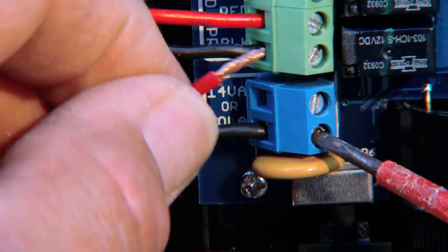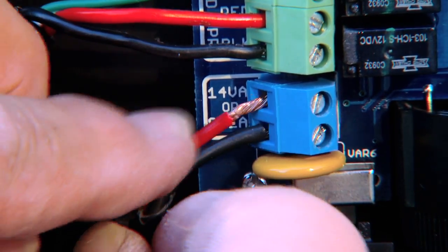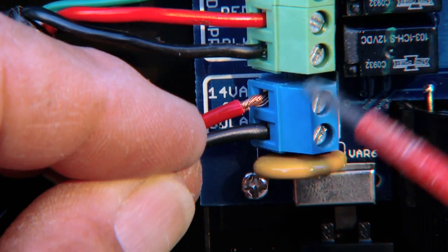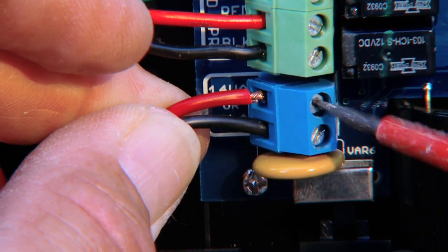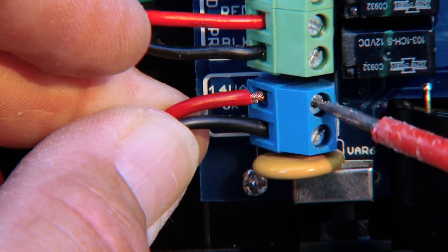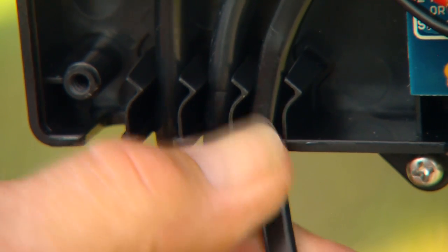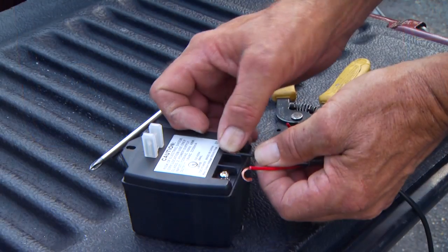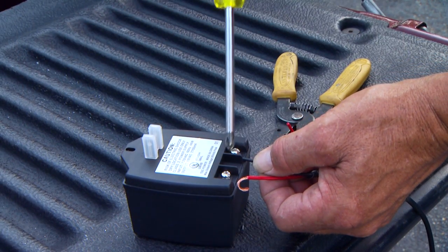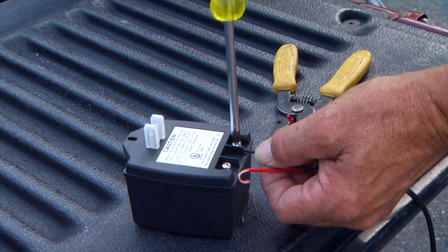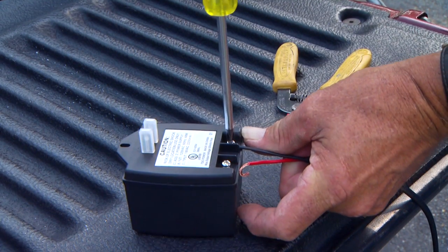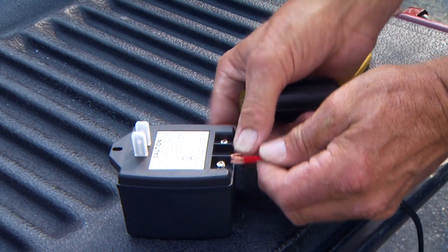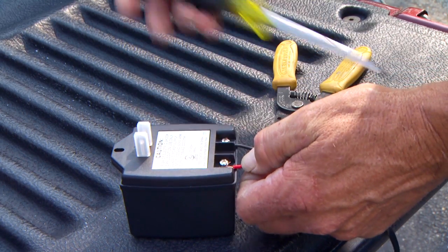These wires can be connected regardless of polarity. Tighten the screws against the exposed ends of the wires and dab with household petroleum jelly to help prevent corrosion. Insert the low-voltage wire through a strain relief slot on the control box. At the AC outlet, strip 1/2 inch of insulation from the ends of the low-voltage wire. Attach the stripped ends to the transformer terminals. Be certain not to let the exposed wires touch each other.